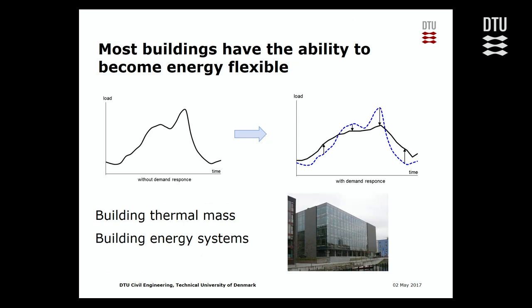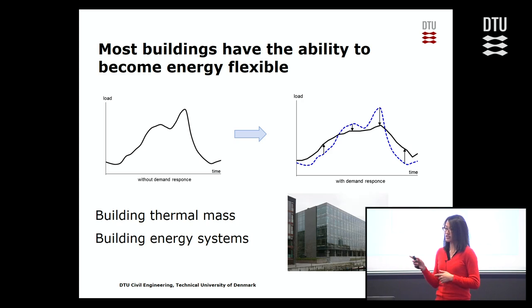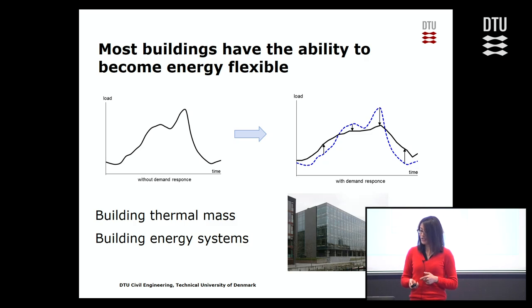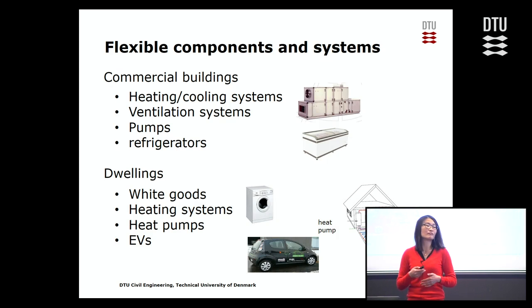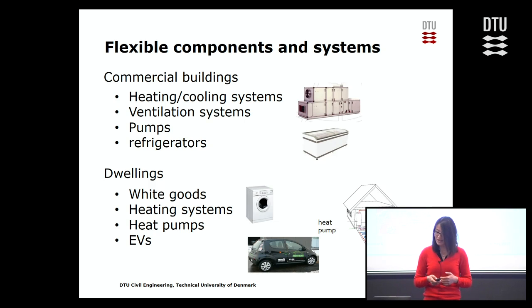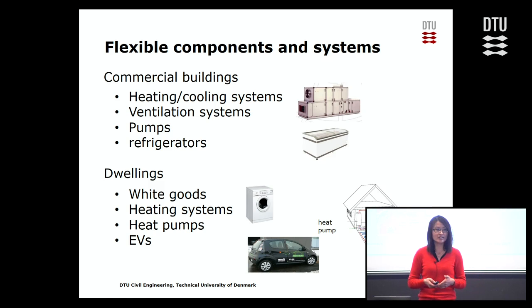The good news is most buildings have the ability to become energy flexible. This is an example of a building tested by DTI. The graph on the left shows the energy demand of a day. By using a demand response program, the energy demand can be changed into a more flat pattern, using building thermal mass and building energy systems. In commercial buildings, heating, cooling systems, ventilation, pumps, and refrigerators have potential to become energy flexible. For example, you can adjust the temperature setting and adjust the flow rate to change the energy consumption of those systems.